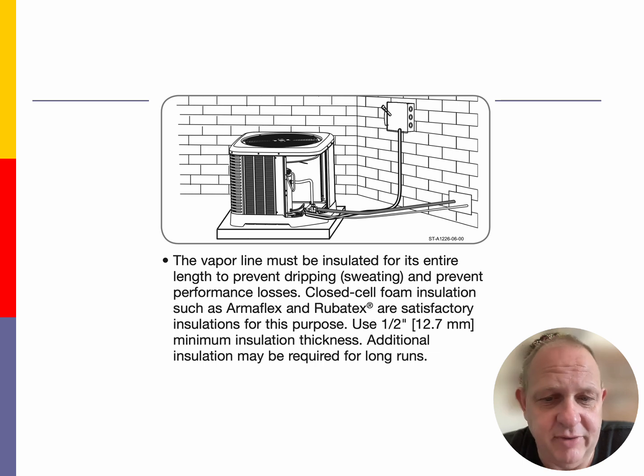That condensation is going to be absorbing heat from the environment, but also, if we do have condensation, it could end up damaging some of the structure if we don't insulate these lines properly. Armaflex insulation and Rubatex insulation are satisfactory installations for this purpose. We'll show you examples in the classroom as we go along. Additional insulation may be required for runs that are longer than that.